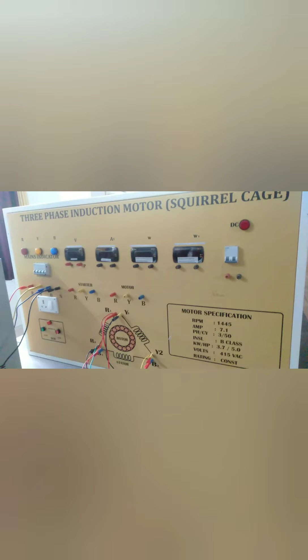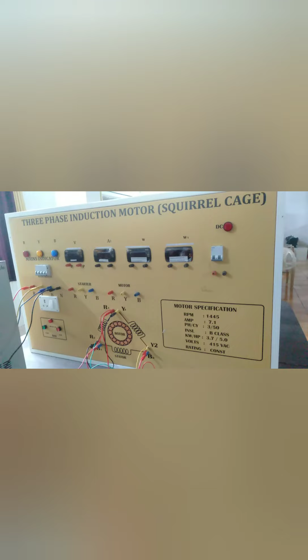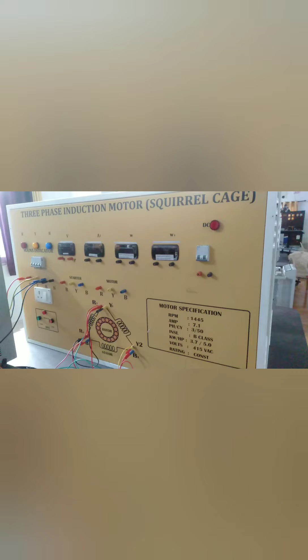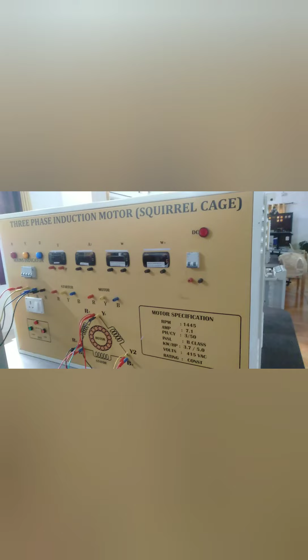If you see on the panel, again the same specification is there which was there during our earlier 3-phase induction motor practical. On the same panel we are doing this practical as well, that is no load and blocked rotor test. Earlier we did the load test on 3-phase induction motor; the panel was the same. The only change is we are not using a starter here, so there is no connection with the starter.